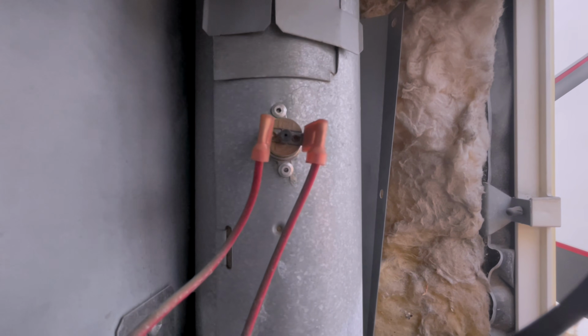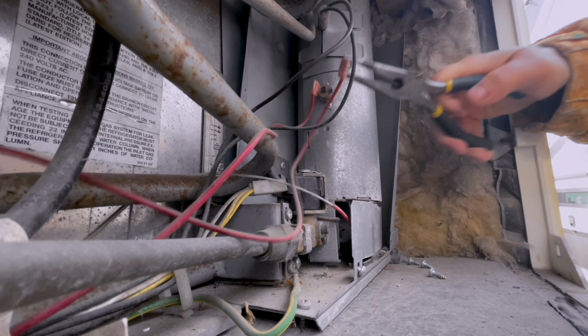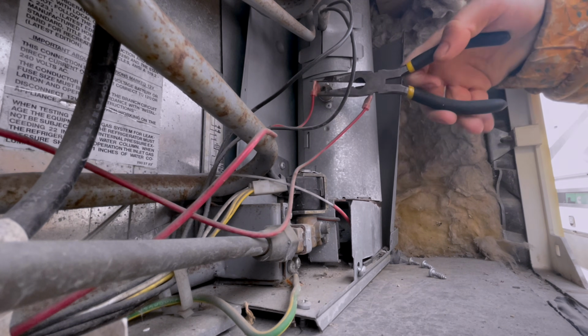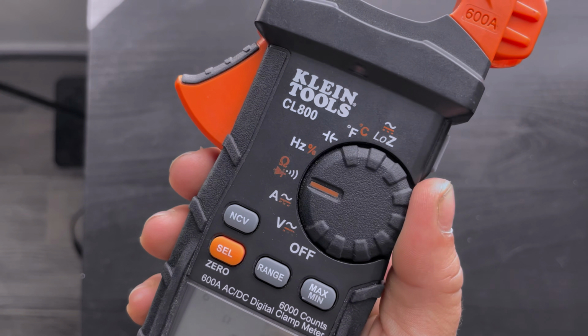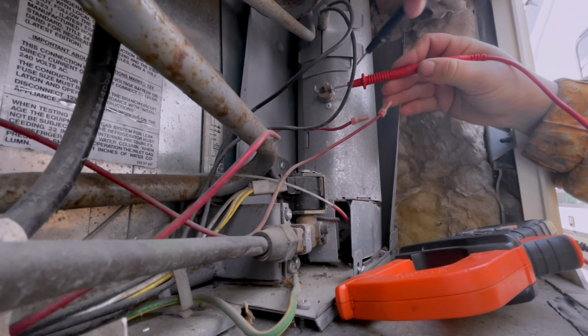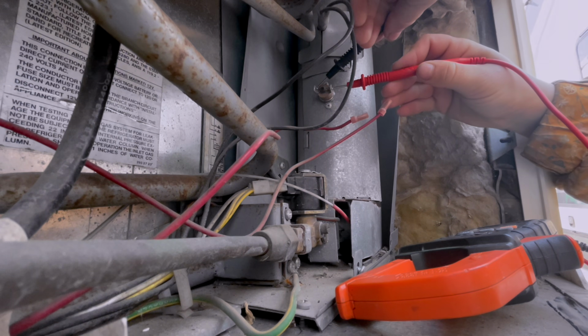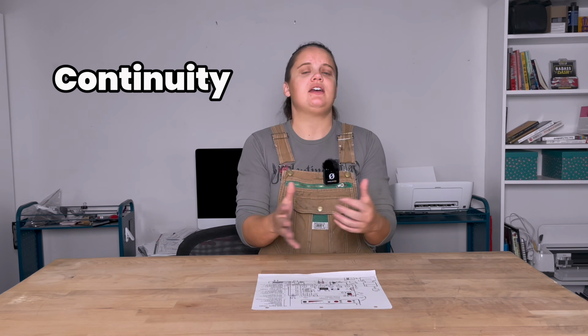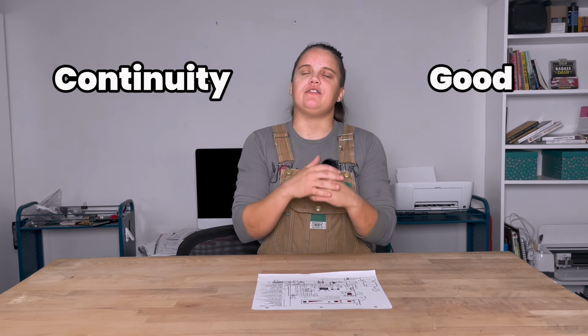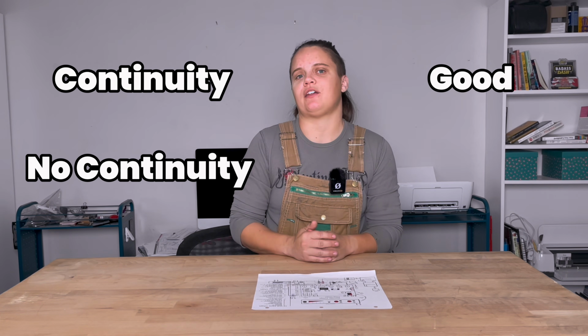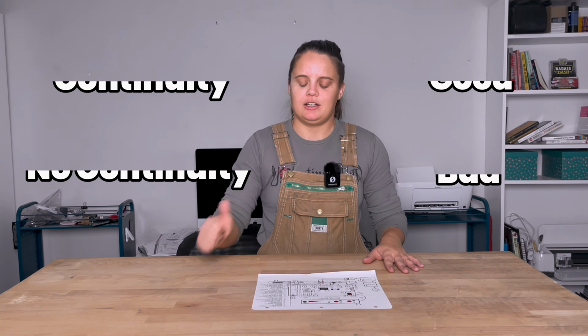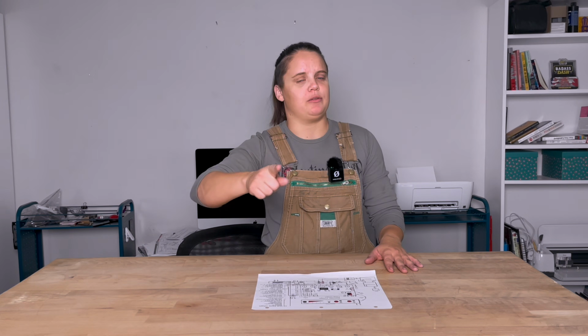You can double check by disconnecting the wires from either side of the thermal disc, setting your meter to continuity, and then putting one probe on either side of the thermal disc. If you have continuity, the thermal disc is good. If you do not have continuity, the thermal disc is bad. Switch that bad boy out and you should be up and running.